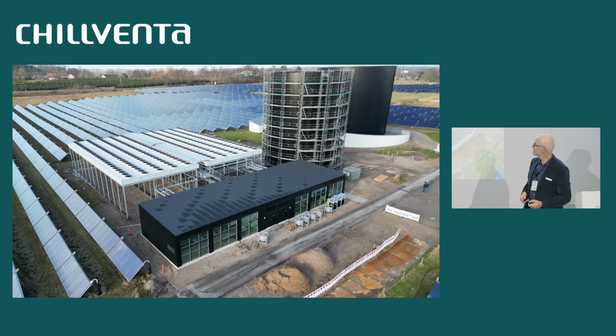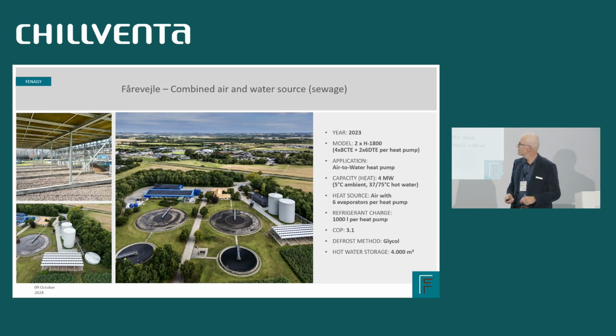Another picture here. There should be a video here, but maybe not. I will see. No, that's okay. This is a combined air source heat pump and wastewater heat pump. So you have the energy collectors here. Here you have the ponds for wastewater, but the wastewater is warm, so why not cool it down before we release it into the river? So we're cooling the cleaned wastewater before it goes into the river. So that's, of course, another nice thing with wastewater. We can use that as the energy source or heat source.